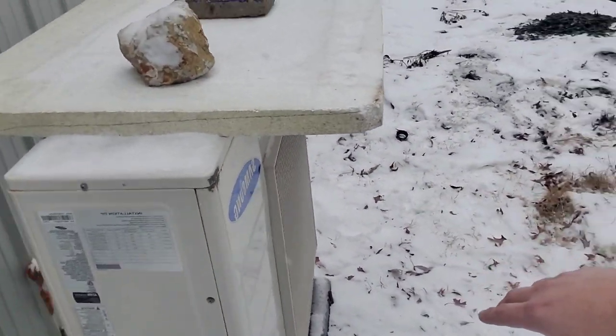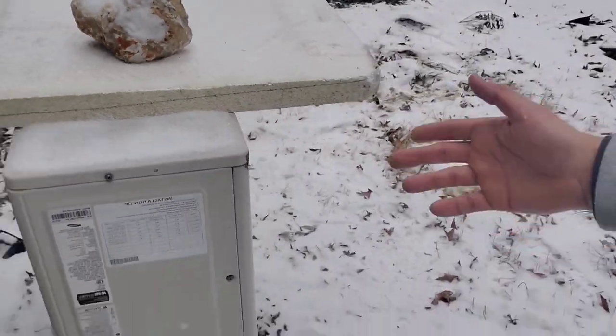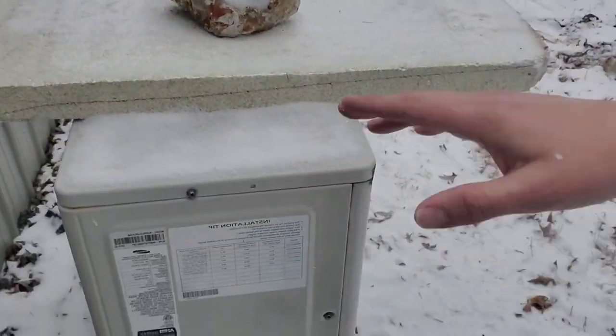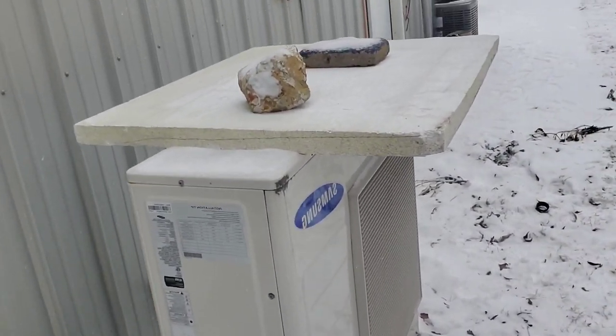What's happening is it's making it so that no air passes across the coil. My equipment is running fine and it's been running fine for days because I got something sturdy and I've had to come wipe the snow off. But if you do this, you're going to have a better chance of your equipment working. Now, this is only for equipment that doesn't have heat strips.